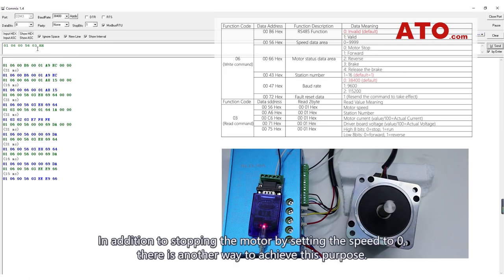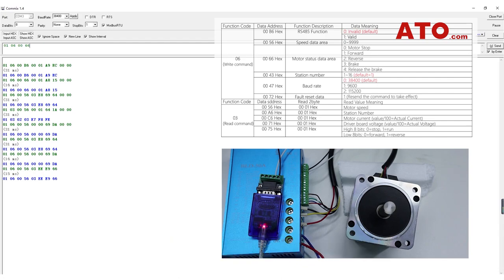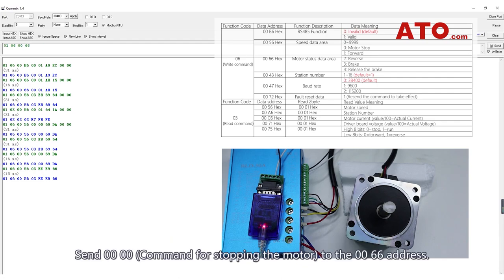In addition to stopping the motor by setting the speed to 0, there is another way to achieve this purpose. Send 0000 command for stopping the motor to the 0066 address.